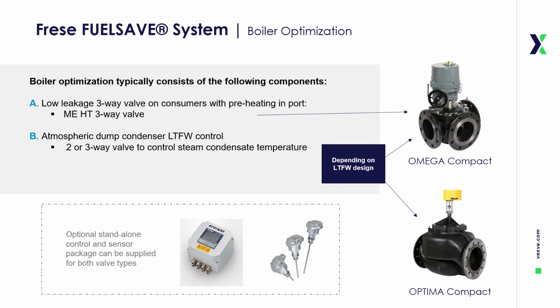The second component is the atmospheric dump condenser, combined with an LTFW control valve, either two-way or three-way, depending on the design of the low-temperature freshwater circuit. This arrangement allows precise control of steam condensate temperature, improving boiler efficiency and protecting downstream equipment. For these applications, Frese offers the Optima Compact and Omega Compact valves.